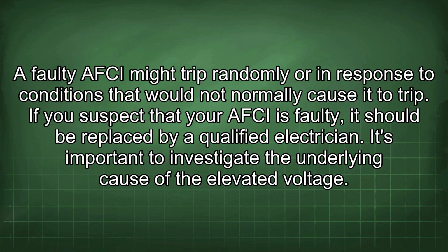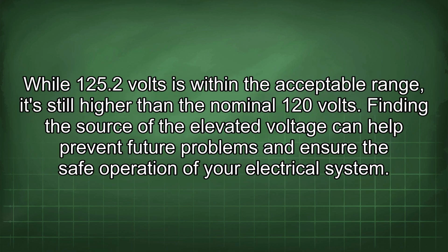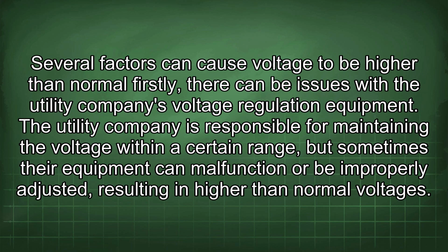It's important to investigate the underlying cause of the elevated voltage. While 125.2 volts is within the acceptable range, it's still higher than the nominal 120 volts. Finding the source of the elevated voltage can help prevent future problems and ensure the safe operation of your electrical system. Several factors can cause voltage to be higher than normal. Firstly, there can be issues with the utility company's voltage regulation equipment. The utility company is responsible for maintaining the voltage within a certain range, but sometimes their equipment can malfunction or be improperly adjusted, resulting in higher than normal voltages.